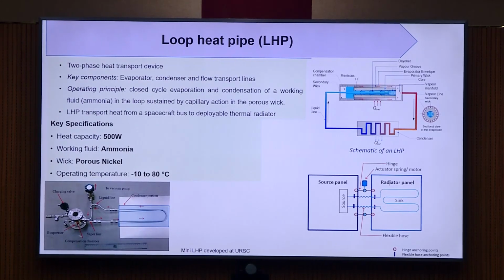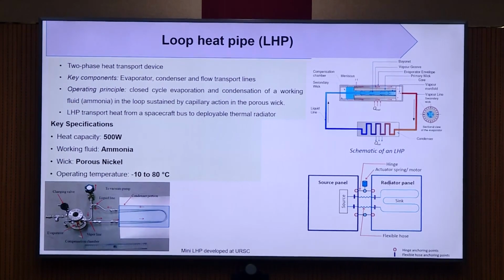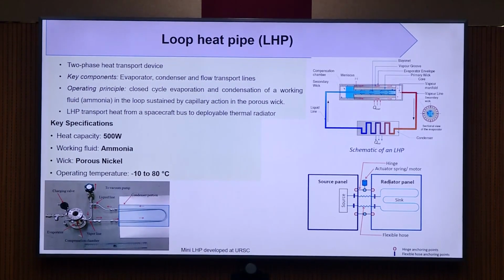Loop heat pipe. There are applications where we cannot manage with a regular heat pipe. There are some applications where the payloads dissipate very high heat, which we cannot meet with regular heat pipes because of limitations like the capillary limit. So when the heat loads are high, we have to have a more rugged system. This leads to the loop heat pipe.